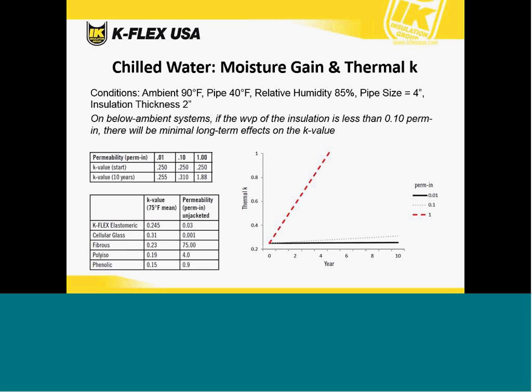The solid black line shows a fairly stable thermal K over the 10-year life cycle of this insulation system because the low initial water vapor permeability prevents moisture from penetrating into that system. On the opposite end of the spectrum, the dashed line shows an insulation system with a permeability of 1 on day 1. Over time, moisture will accumulate in that system, which will drive up the thermal K, which will cause you to lose the efficiency of the insulation system. It may cause you to lose the efficiency of your piping system and the water temperature there. It may lead to mold growth and corrosion under that insulation. So keeping the insulation system dry keeps performance stable over the life of that system.